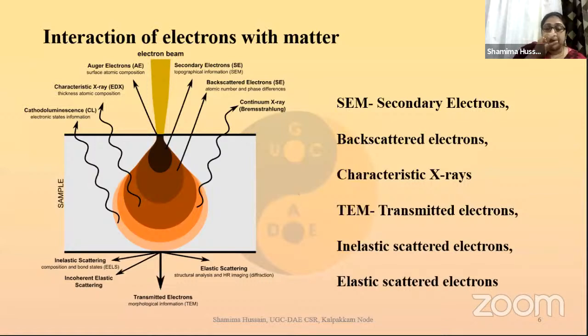This is because your interaction volume is only limited to as much as your probe is entering. So if I could further take my probe down, this value would change. So we use these characteristic X-rays just to understand the elemental composition of the material. Other than that, this is where the electrons have come back, the primary beam has come and reflected back, and beyond this side is the transmitted electron.